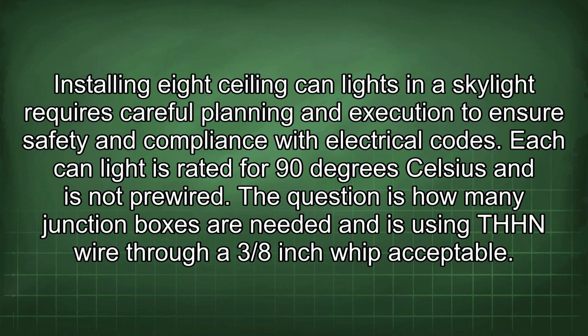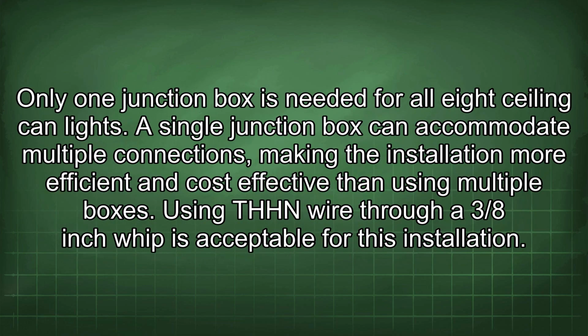Installing eight ceiling can lights in a skylight requires careful planning and execution to ensure safety and compliance with electrical codes. Each can light is rated for 90 degrees Celsius and is not pre-wired. The question is how many junction boxes are needed, and is using THHN wire through a 3/8" whip acceptable. Only one junction box is needed for all eight ceiling can lights.